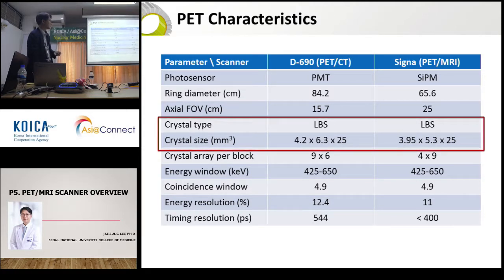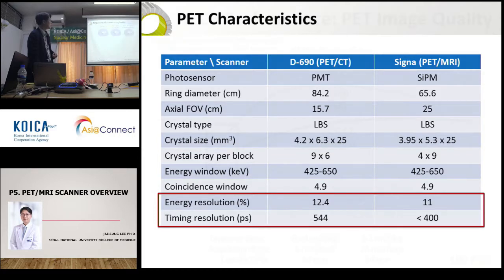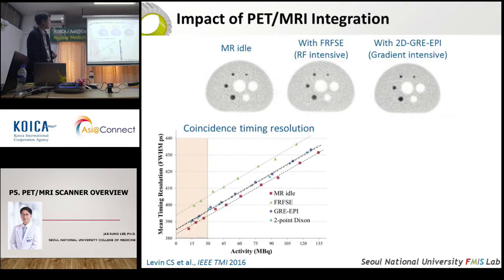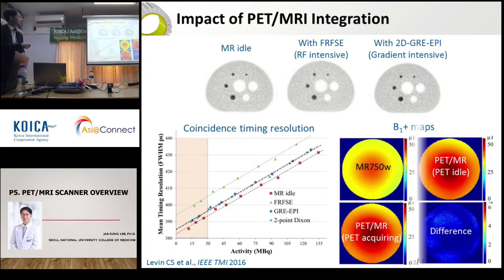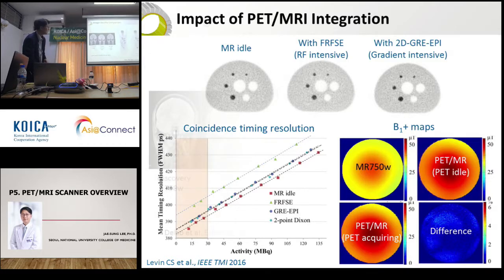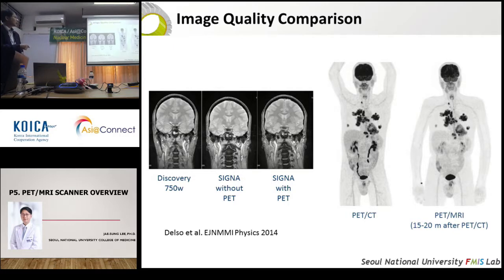In comparison with the PET-CT, the PET in the PET-MR has a smaller ring diameter but a longer axial field of view, 25 centimeter. Both Siemens and GE use a 25 centimeter axial field of view, so they are quite equivalent in terms of their dimensions. They use LYSO crystals with a smaller size than the previous systems. But as I told you, they have good timing resolution, better than their previous systems.